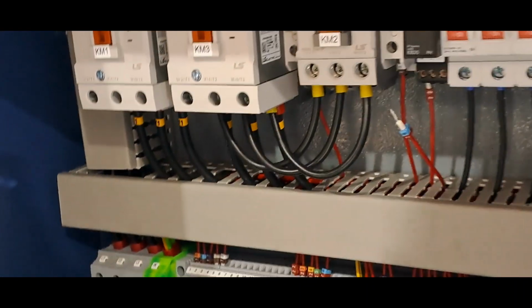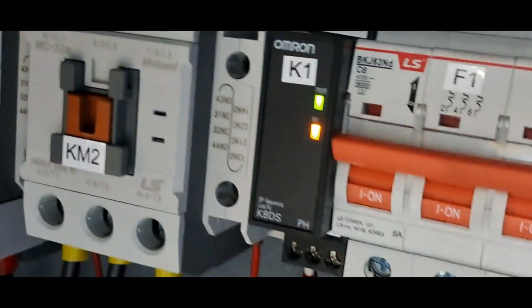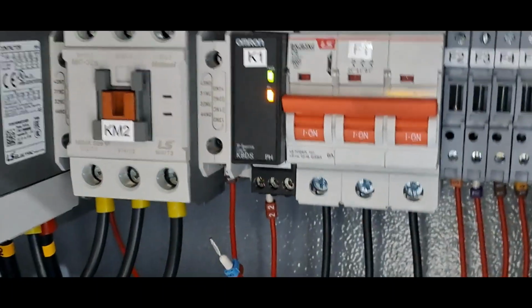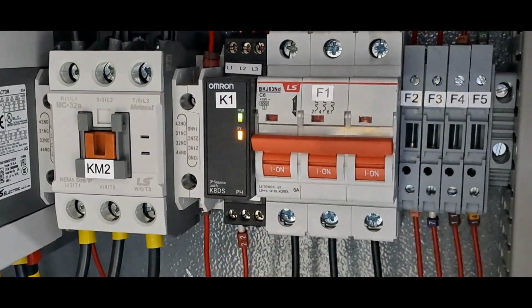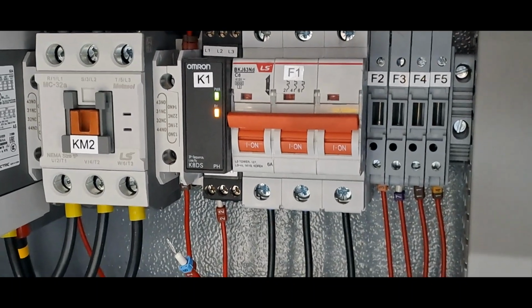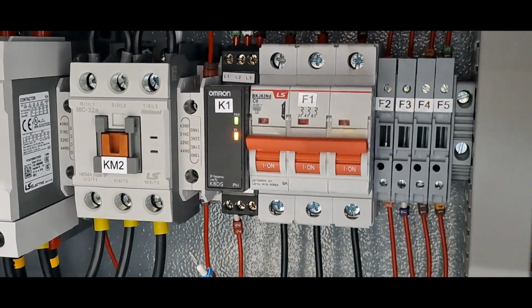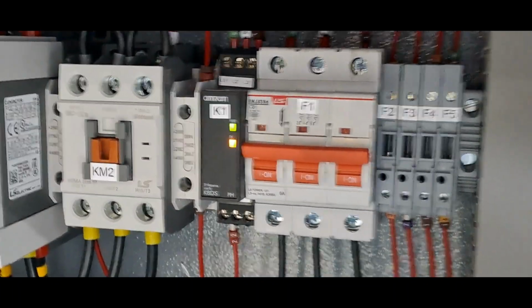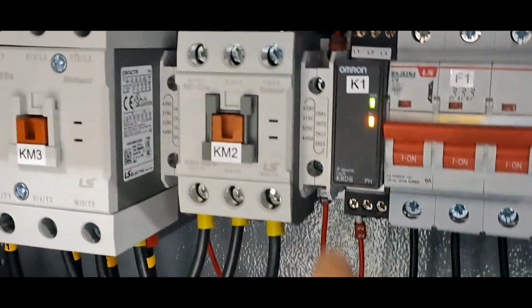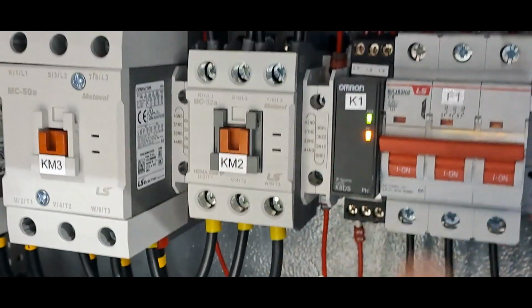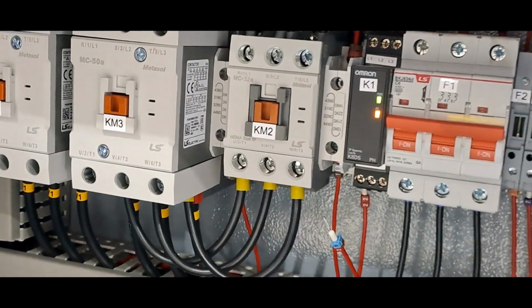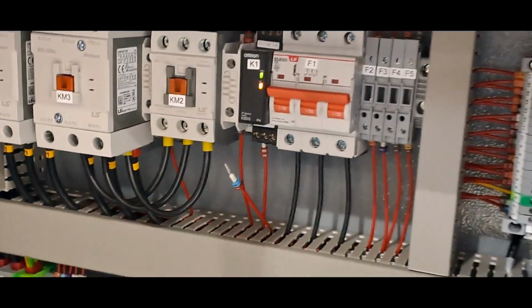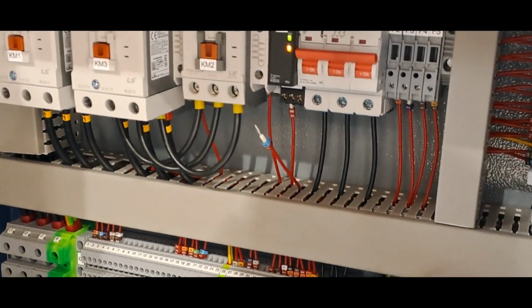Alright, just to add further, if you see this K1, Omron K8DS, basically this is a phase detector, and also detects voltage. So it detects the current and the phase. If the voltage drops below 380 volts, it will cut off the line. This NC connection will become NO, and it will give an error fault through the system, a power asymmetric fault. Okay, so in case the system shows you this error, verify the R, Y, B on top, this 1, 2, 3.